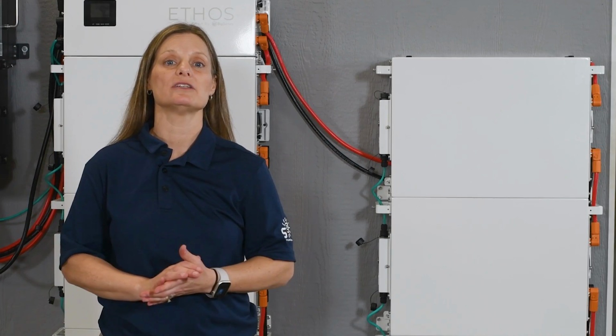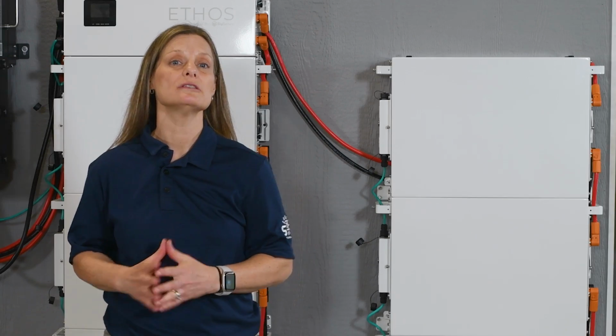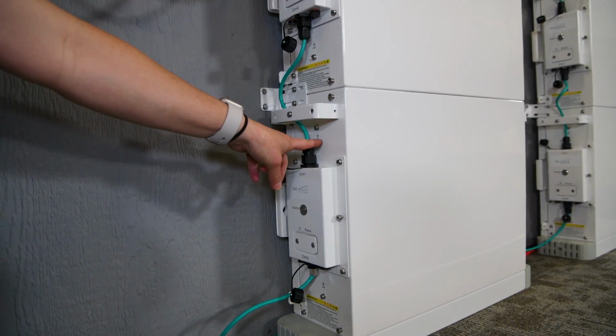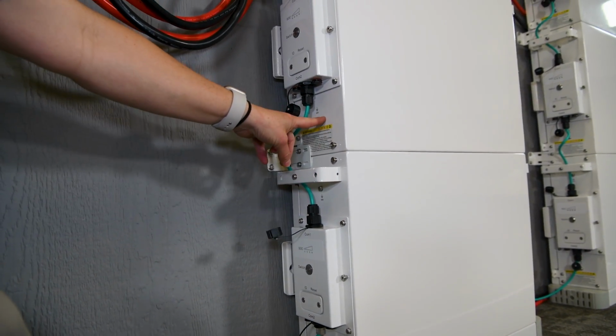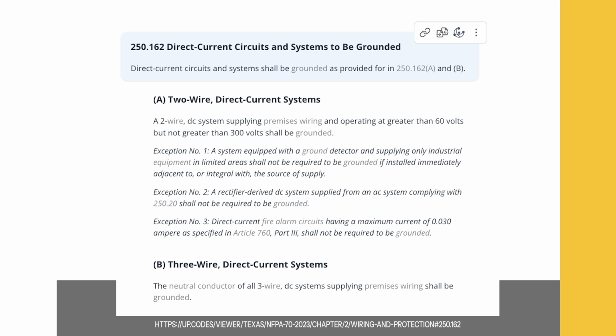So far, we've not touched on the subject of the grounding screws. BigBattery has prioritized safety by incorporating grounding screws into each module. It's interesting to note that according to the National Electric Code, grounding isn't required for DC systems operating below 60 volts. So for these 48-volt batteries, grounding remains an optional but recommended safety measure.